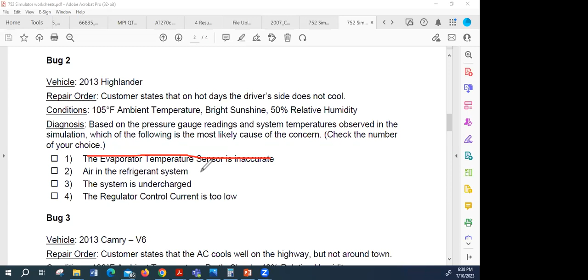Right, but if there's air in the system, the air is circulating. The air will be in the low side, no big deal, then the air will get to the compressor and go in the high side. And all of a sudden, because the air will heat up, and air changes pressure a lot with temperature, it'll actually make spikes. Your high side pressure, the needle will be spiking like this. That's real common for air in the refrigerant, so I would go with number two.